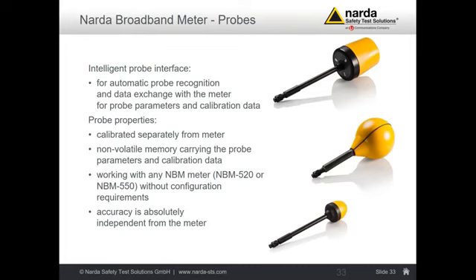This is okay for the standard calibration of the meters. If you have an accredited calibration of such a meter, then this accredited calibration is only valid for a specific basic meter connected with a specific probe. So there you no longer have the allowance to change between different probes and different basic meters. Your accredited calibration report is only valid for the combination which was calibrated at that time.